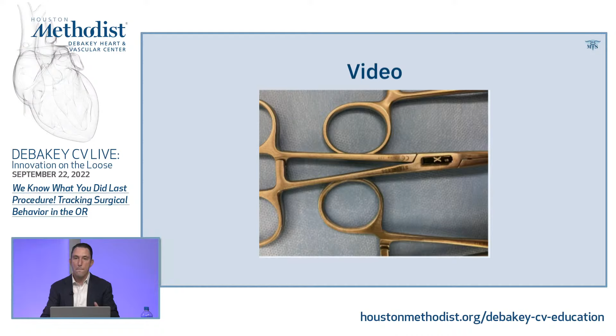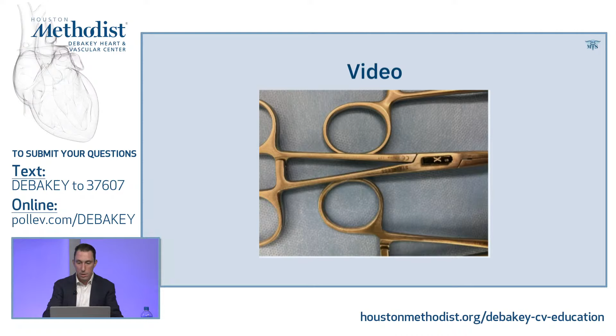And the way they could be affixed to these instruments, they could be embedded at the point of manufacturing, or retrofitted by using an FDA-approved and cleared epoxy and adhesive mixture. And these mixtures survive the autoclave cycle for up to 100 autoclaves, and sometimes 6 times the survivability rate of the instrument. So what does that mean? The instrument is more likely to fail than the tag is to fall off. But here's some videos to kind of give you an idea of how this system fits into the workflow in the operating room.